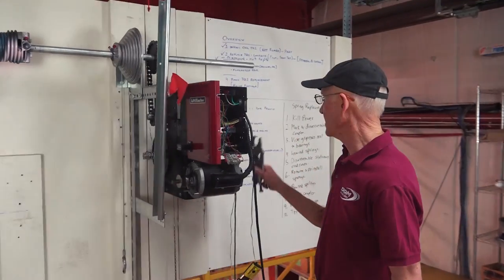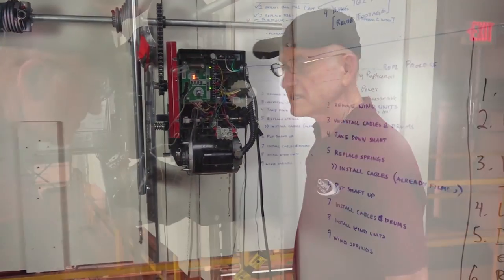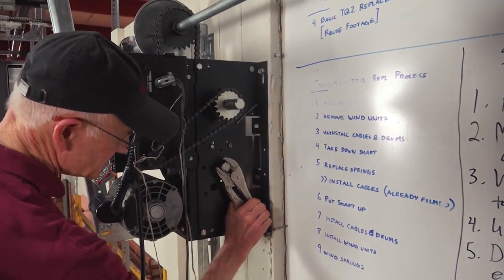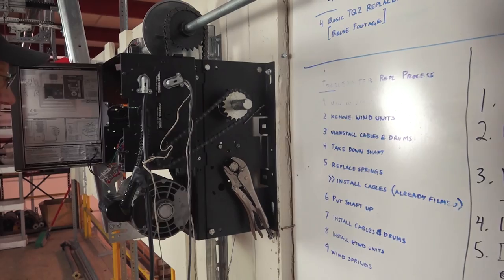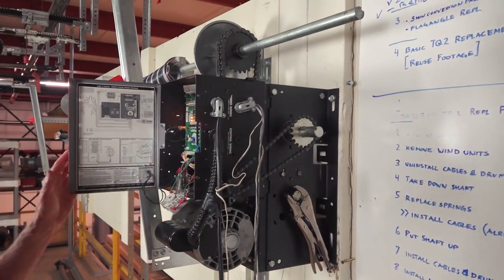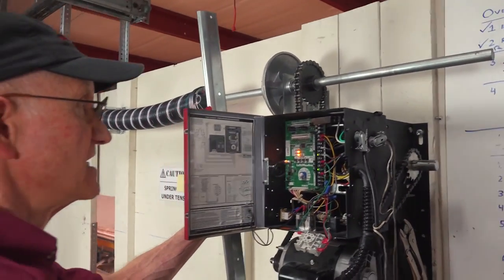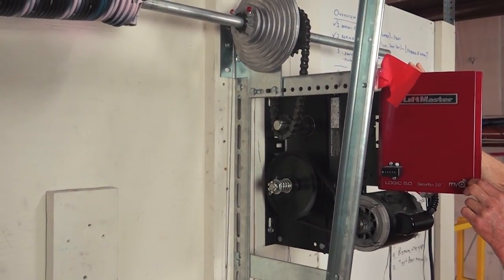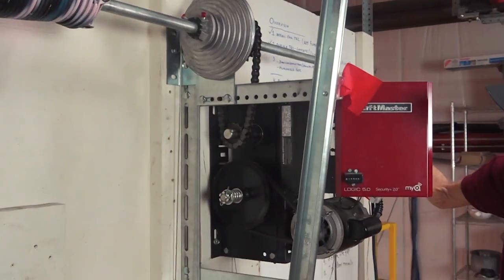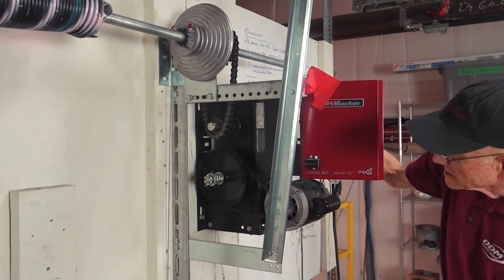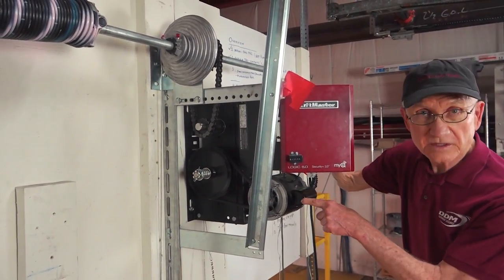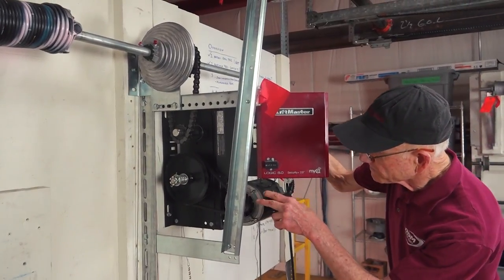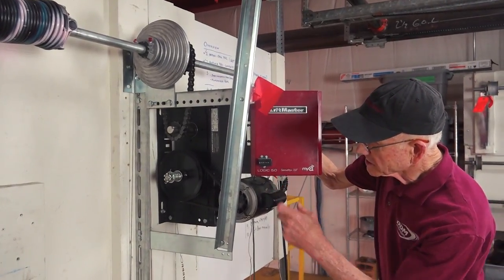I'm going to put this vise grip on the clutch shaft. Put the vise grip on the clutch shaft and then push the up button. And when I do that, notice when I have the vise grip on there, if I push the open button, it starts to turn. Did you see the motor turning? The motor starts to turn, but the pulley doesn't turn.